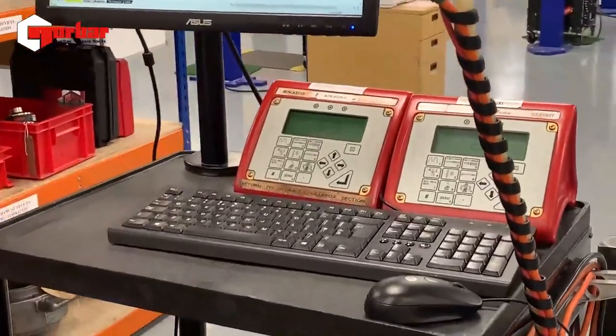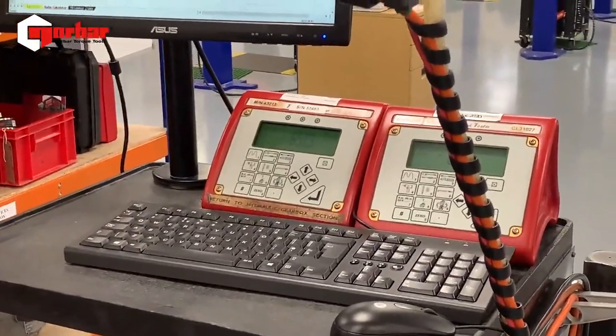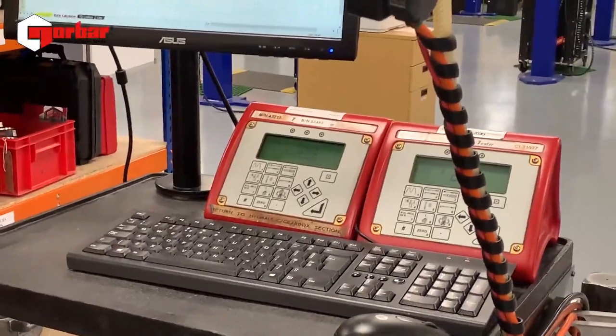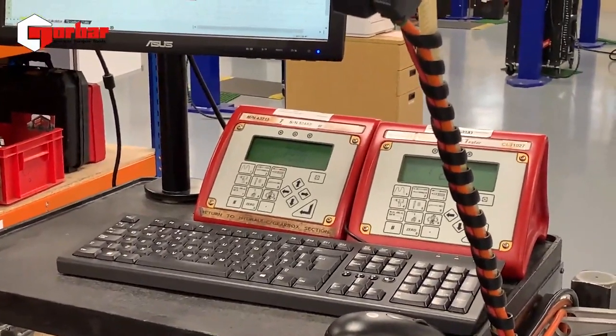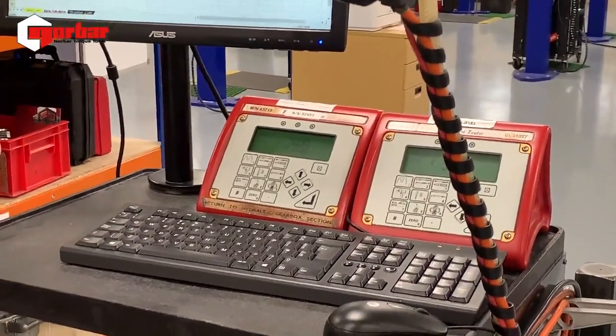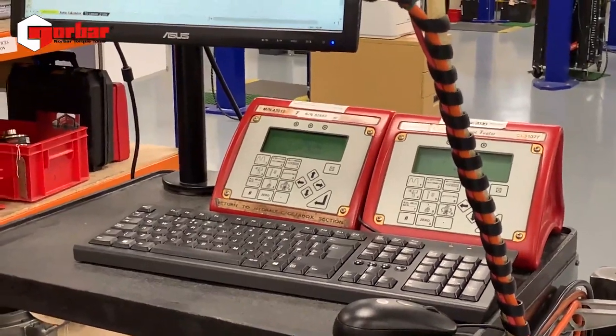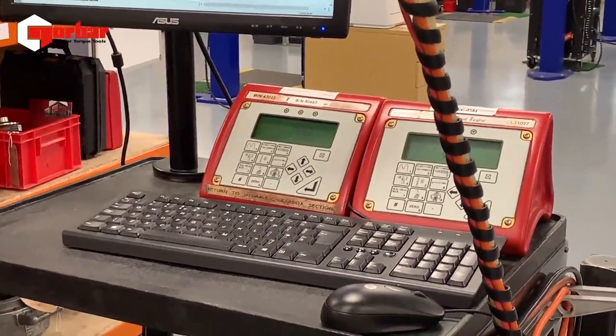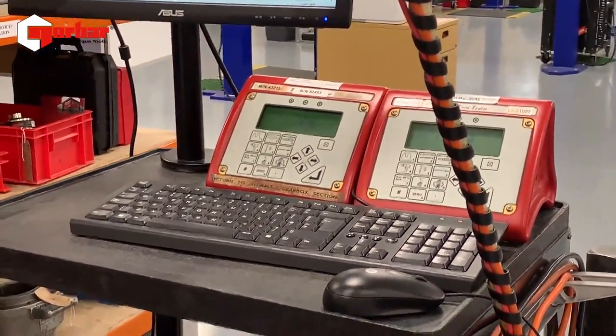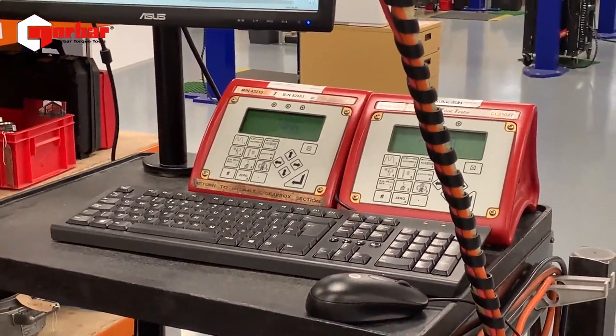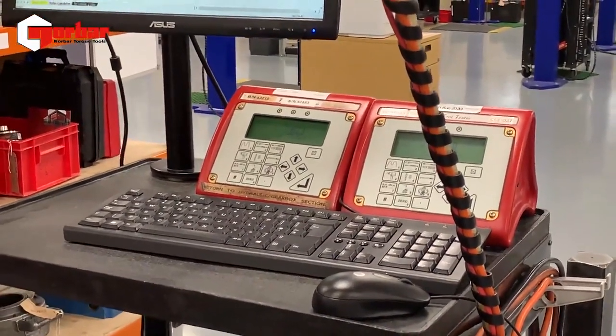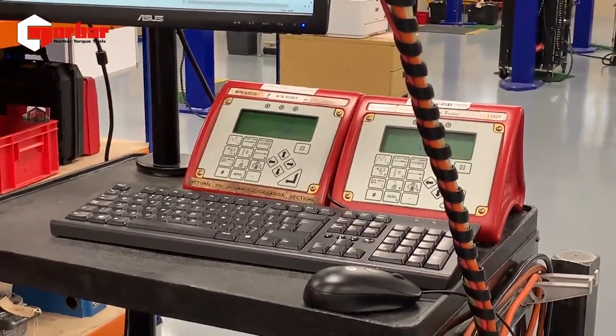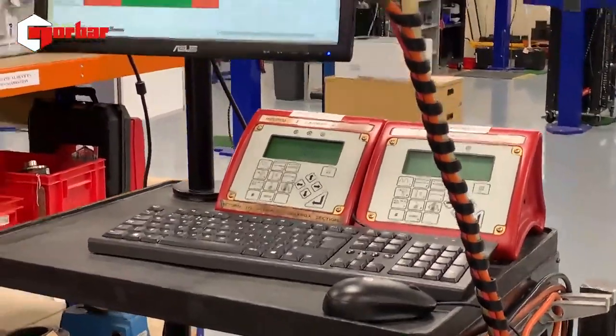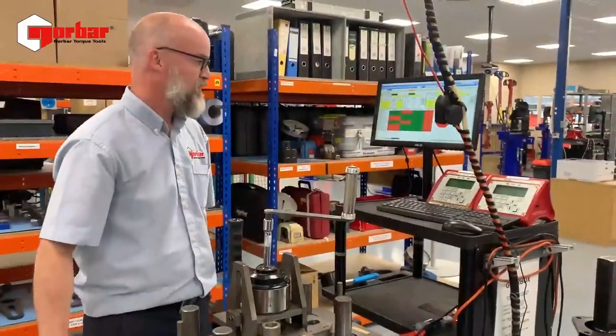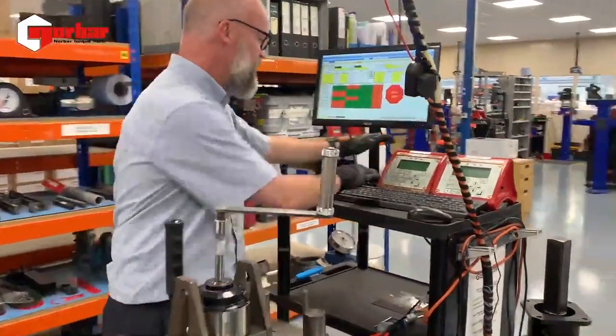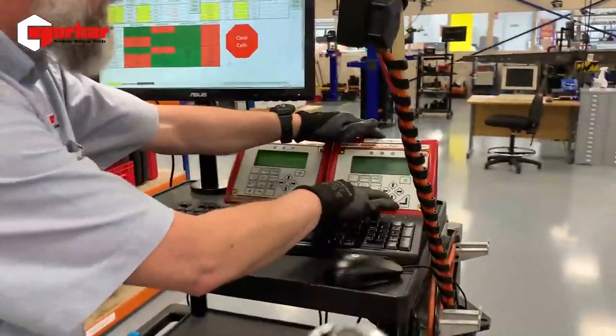This is a test or demonstration HT, and the results are as found, and they are always as found because there is no adjustment you can make to a HandTorque. The calibration or the ratio depends on the ovality of the annulus, the way the gears have been cut, and at the low end you can also get frictional characteristics. But this gives you the ability to say to your end users, your customers, what that HandTorque multiplier is delivering. Okay, so with zeroing our transducers, we're zeroing them in track mode.